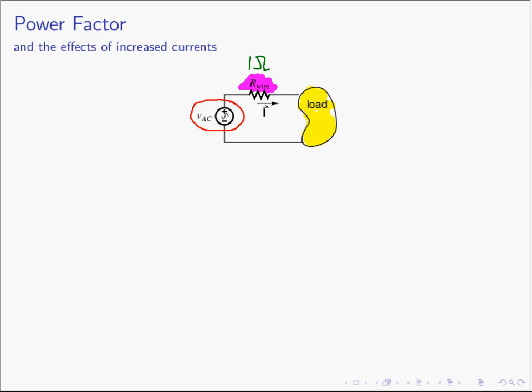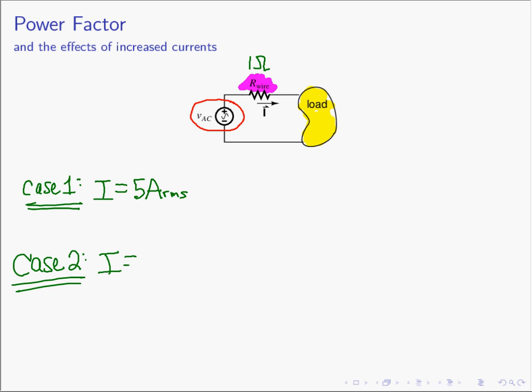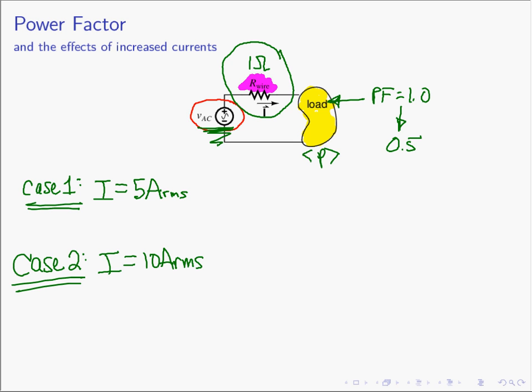Let's go back and look at what we had before. In case one, with unity power factor, the current was 5 amps RMS. In case two, when our load had a power factor of 0.5, the current had to increase to 10 amps RMS to maintain the same average power to our load. Notice that if we take our load and reduce the power factor from 1.0 down to 0.5, the utility generator and the distribution system have not changed. Let's look at what happens to the power in the wire.